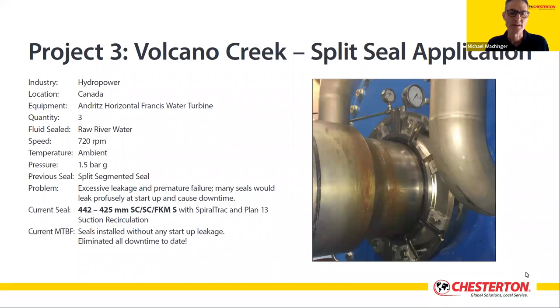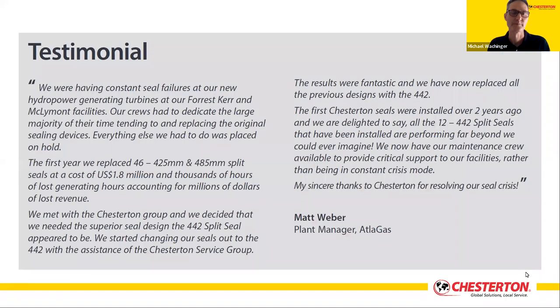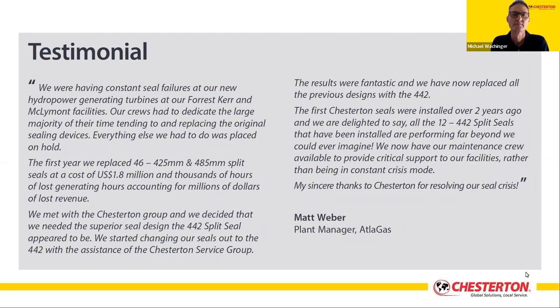Recently, an experiment has been undertaken to completely eliminate the clean flush water, as the river water is considered clean enough to provide seal face lubrication. The cleanest possible flush system will remain on standby, but so far things are looking good. Matt Weber is the plant manager responsible for all three sites at AltaGas, and he sent a lovely note about the experience. If you wish to have Matt Weber's email address, he's more than happy to talk to anybody about his installations.